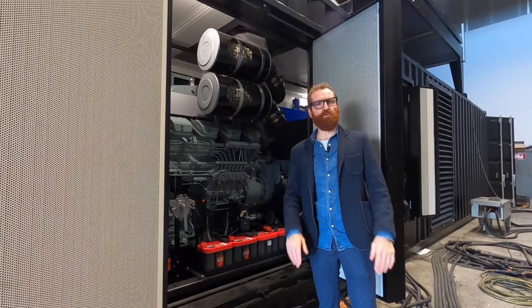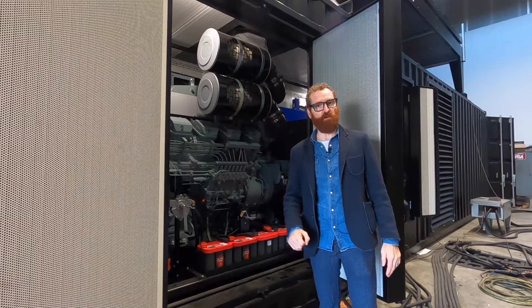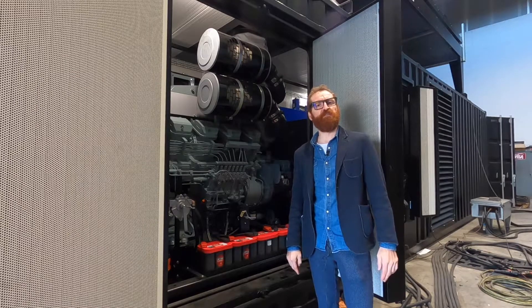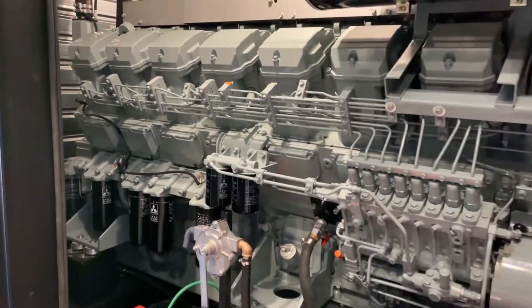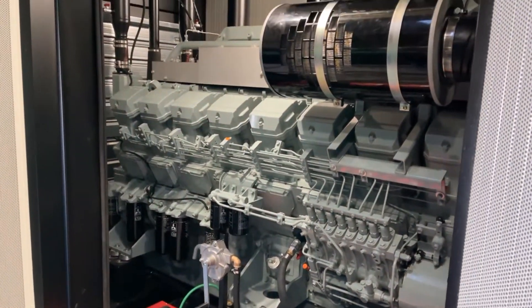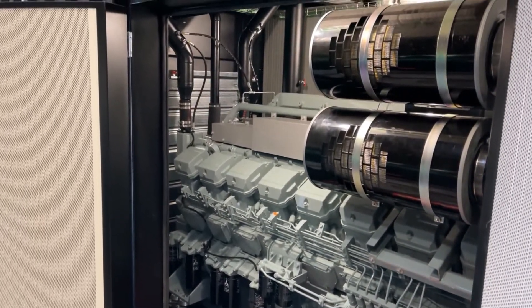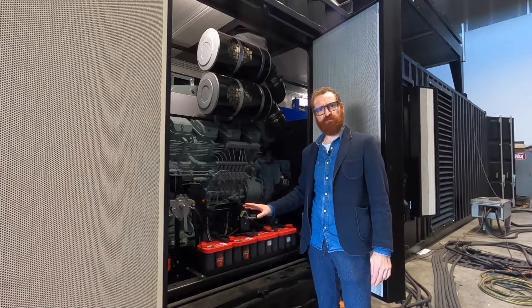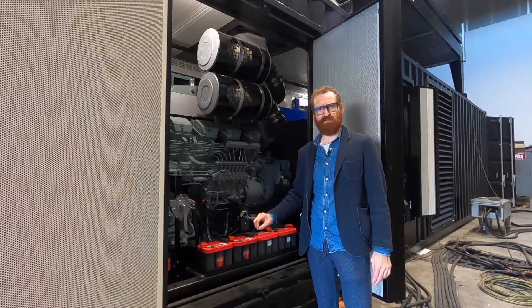The unit is designed to operate in a data center in Holland. It consists of two units, each with a 1,700 DCP KVA rating, powered by a 16-cylinder Mitsubishi engine. Each unit is equipped with a redundant starter system, a double battery pack, each provided with a dedicated battery charger.